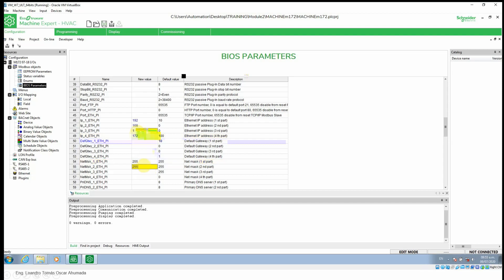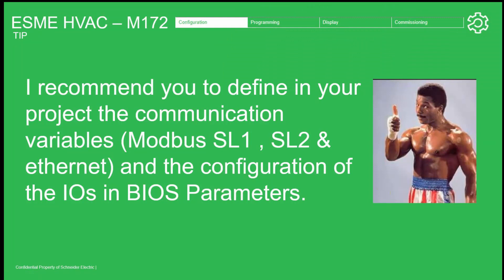This is the same as default but I'm going to change it anyway. So these are the initial configurations — this is all regarding the BIOS parameters. When we perform a full download, the software is going to ask us if we want to download these parameters. My recommendation is to always configure all the communications variables before starting with the project — it will be much simpler later and we avoid mistakes like not being able to communicate because we haven't defined anything in this part.